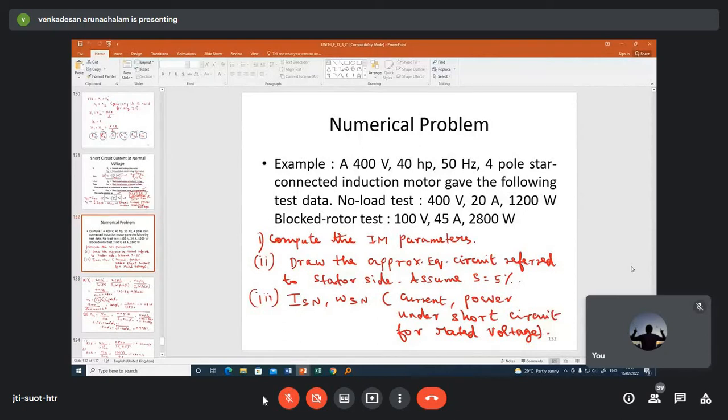Then after computing the induction motor parameters, draw the approximate equivalent circuit referred to the stator side, and please assume the slip is 5%. And then you have to compute the current and power under short circuit condition for rated voltage. That is nothing but ISN and WSN. ISN is the current under short circuit condition for rated voltage. WSN is the power under short circuit condition for rated voltage. So this is what we compute.